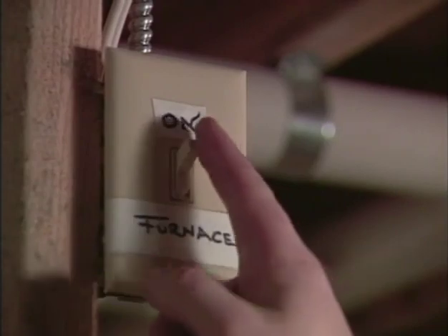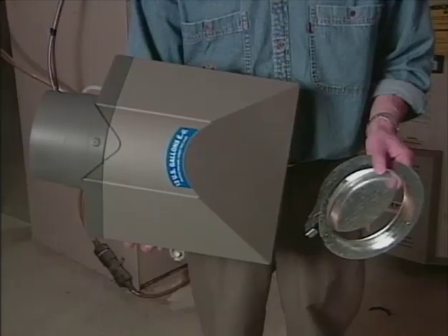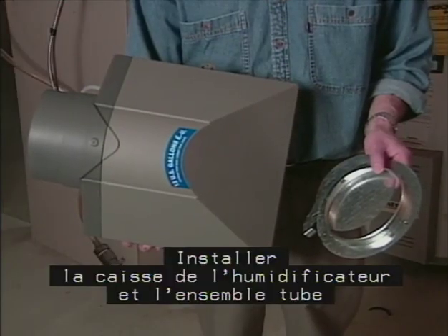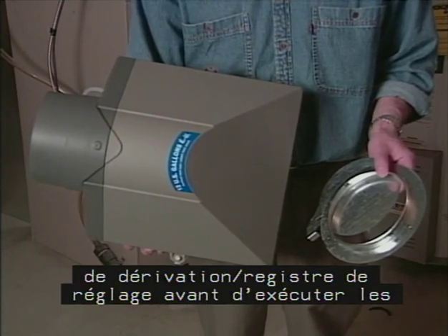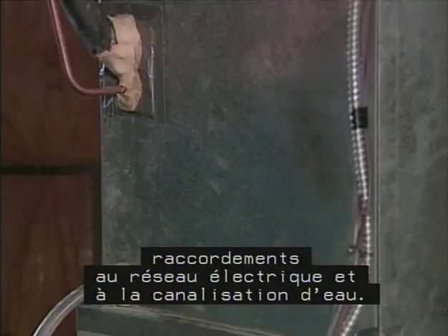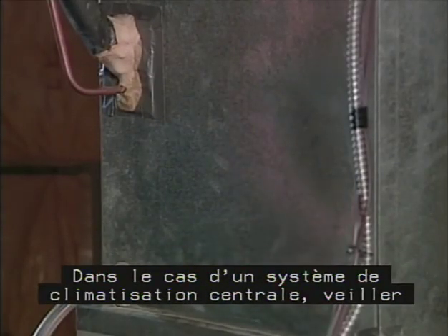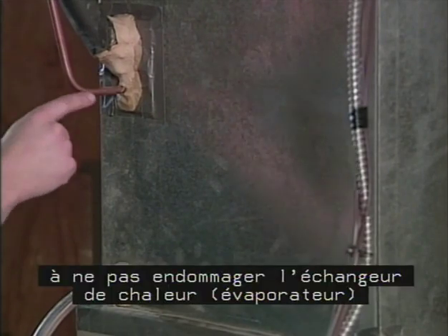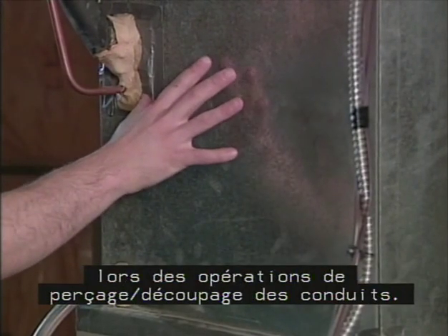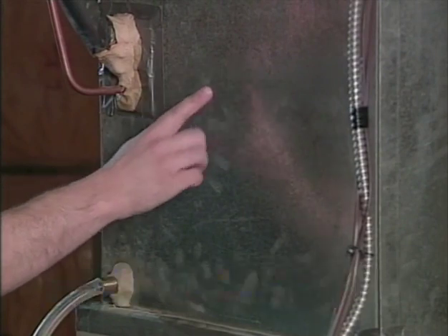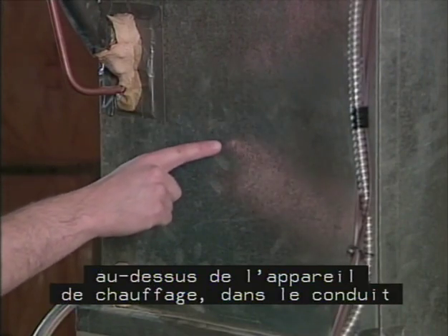Turn off power to the furnace. Install the humidifier cabinet and bypass collar and damper before you make any electrical or water connections. If you have central air conditioning, take precautions not to damage the evaporator coil when drilling and cutting into the ductwork. The evaporator coil is generally installed just above the furnace in the supply duct.